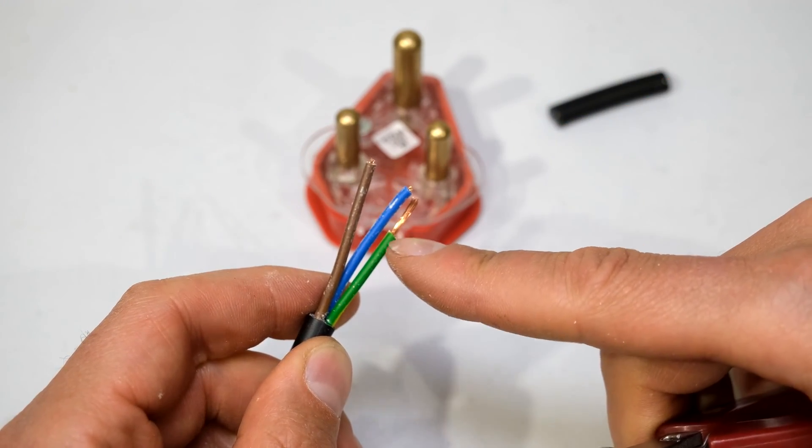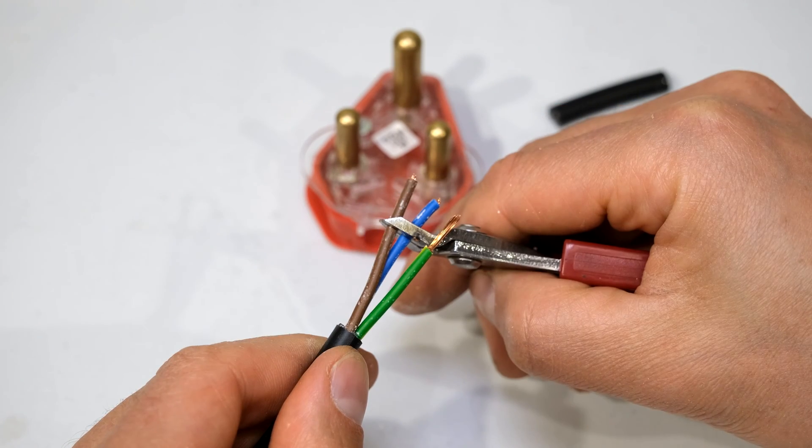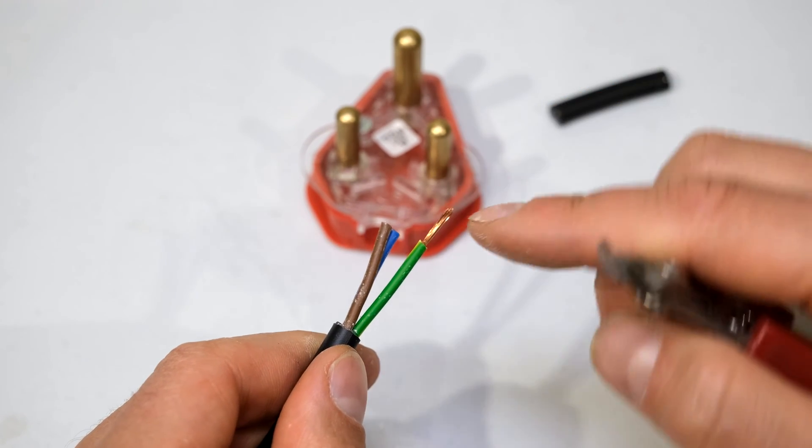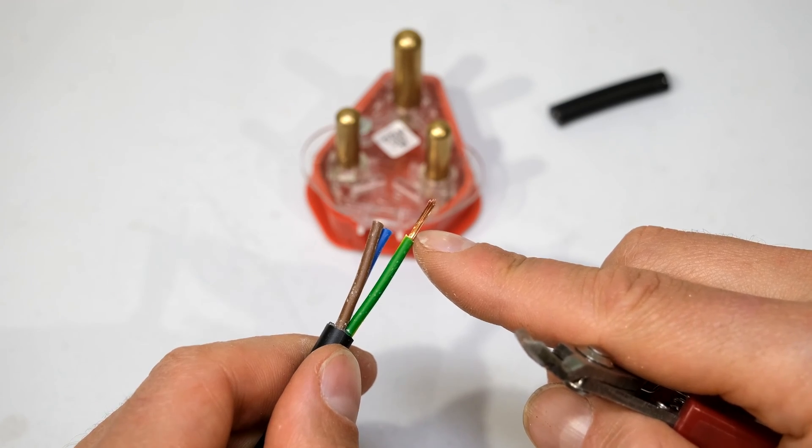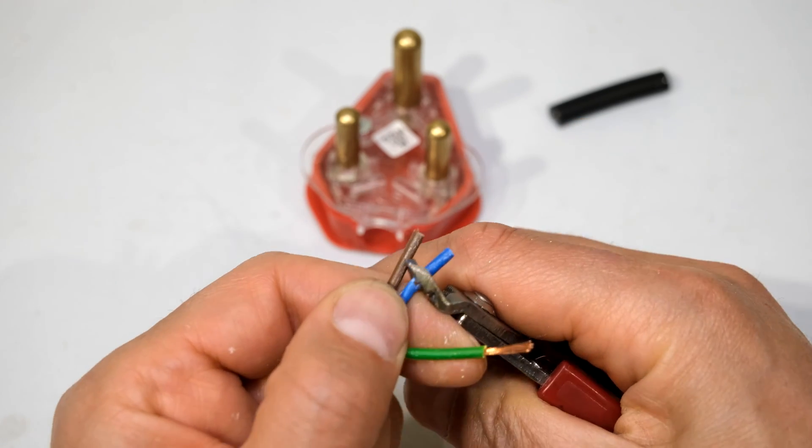A safety precaution is to keep the earth wire longer than the live and the neutral. So what I do is I cut the blue and the brown wire at the level of where I removed the insulation of the earth wire.